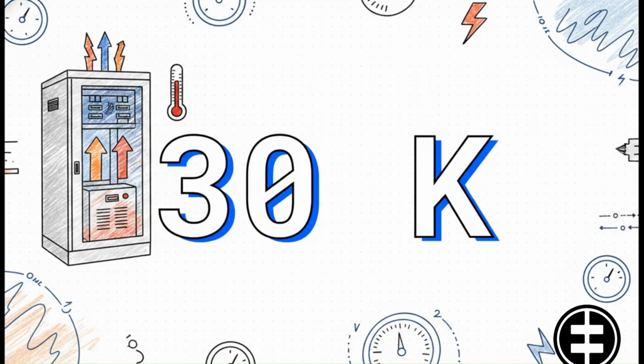So during these tests, once the assembly is loaded up and the current is flowing, it takes about 8 solid hours for the internal conditions to stabilize. And the strict, absolute limit here? The average temperature rise of the air inside the assembly must stay strictly below 30 Kelvin. And just a quick note, we use Kelvin here to measure the specific temperature rise from the ambient baseline. This makes sure that even under maximum operating conditions, we aren't literally melting the internal environment.